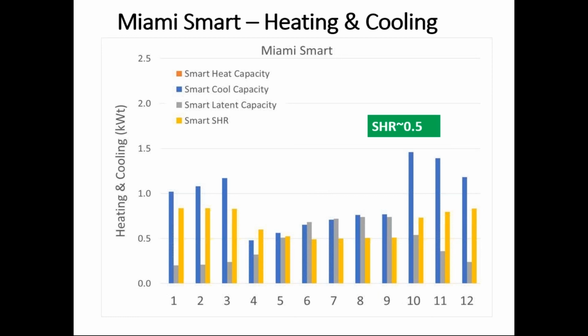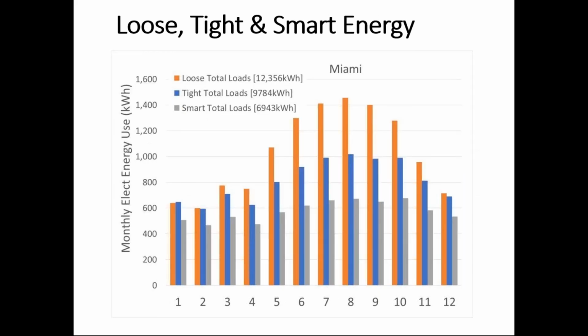But this is basically showing that by sealing it up and ventilating smart, we can get to a level where most of the cooling can be managed with, say, today's high-performance air conditioners, and putting it in dry mode, which is still a very efficient way to remove moisture. And then for those exceptional times, maybe still having a dehumidifier, but not having to use it as often. But basically getting moisture under control by sealing it and then ventilating as you need for air quality needs.